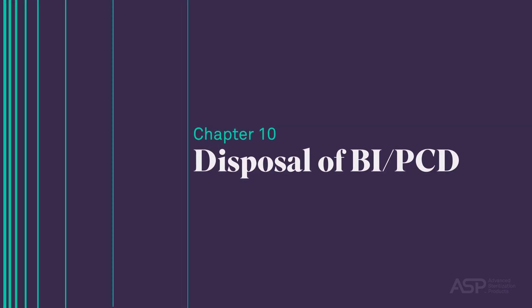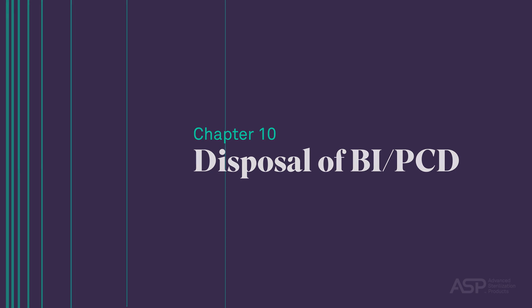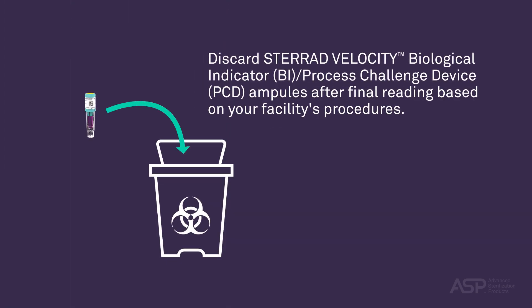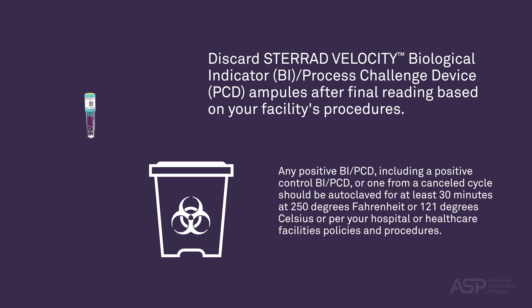Disposal of Biological Indicator Process Challenge Device. Discard STERRAD VELOCITY BI PCD ampules after final reading based on your facility's procedures. Any positive BI PCD — including a positive Control BI PCD or one from a cancelled cycle — should be autoclaved for at least 30 minutes at 250°F (121°C), or per your hospital or healthcare facility's policies and procedures.